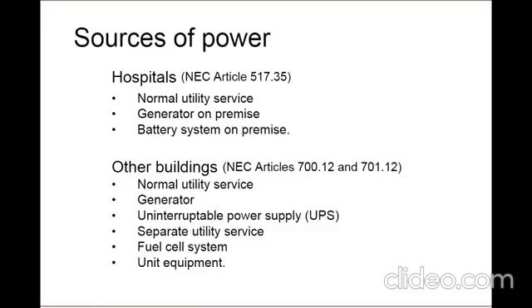Here we see a list of acceptable sources of power for a hospital. In a hospital, there must be two sources of power for the essential electrical system. The normal supply is typically the utility, but could also be an on-site generating plant. The alternate source may be either a generator or a battery system. The source must be located on-site. If the normal supply is an on-site generating plant, then the alternate source may be an external utility service. You'd have to check with the hospital governing body or the local AHJ to confirm that, though.